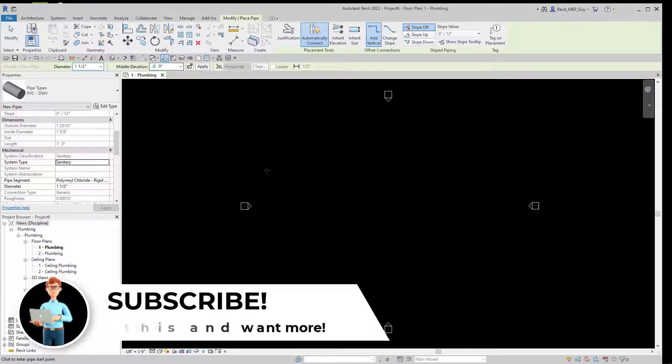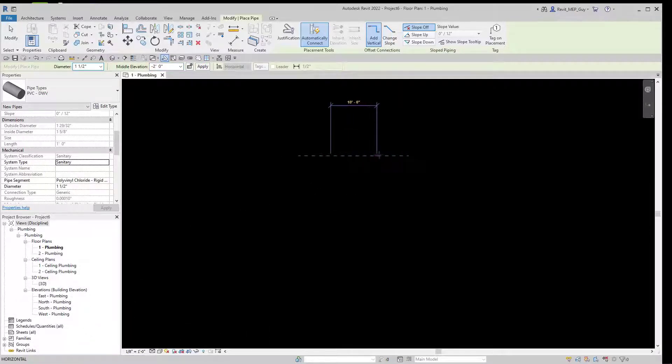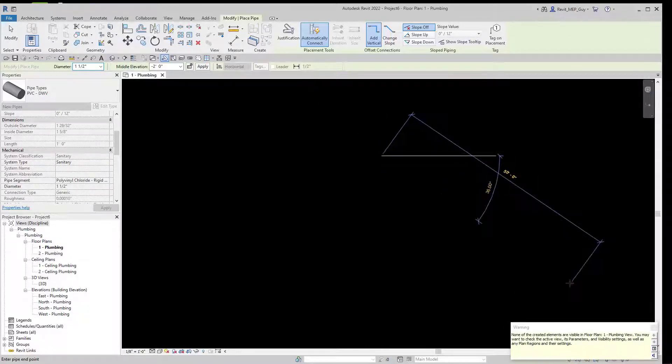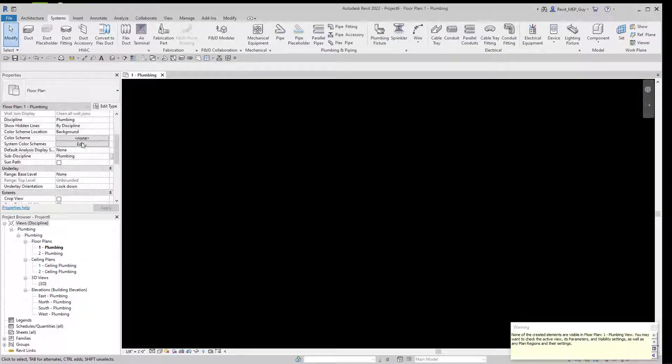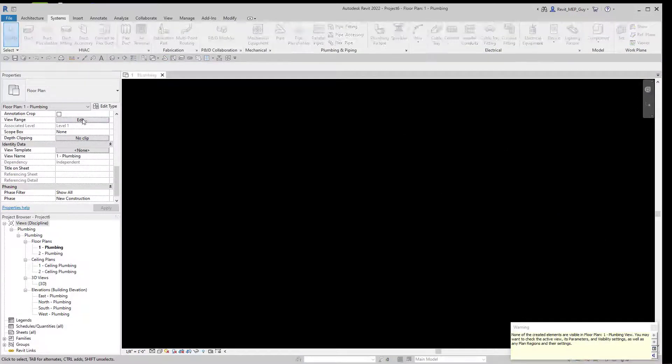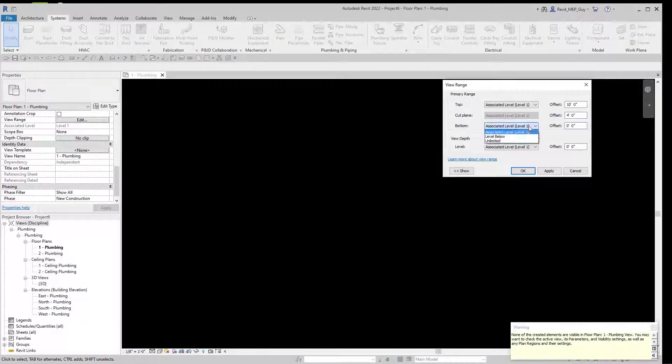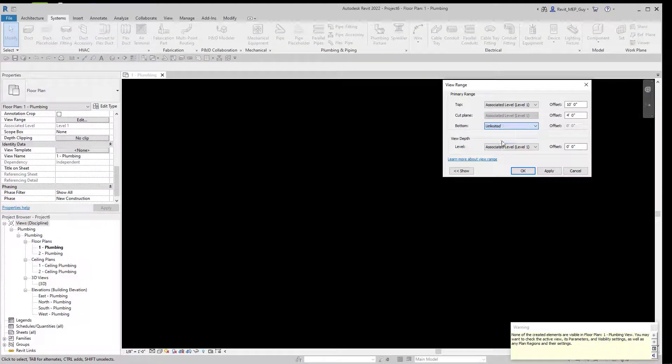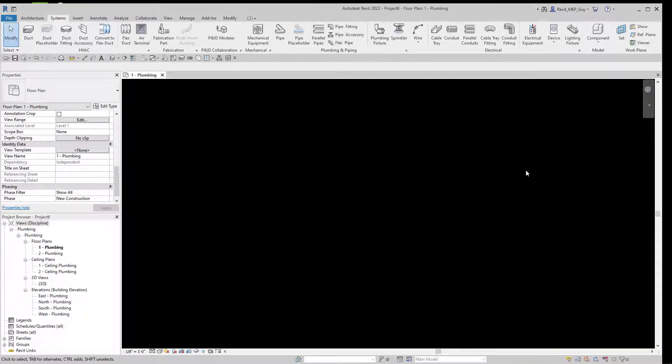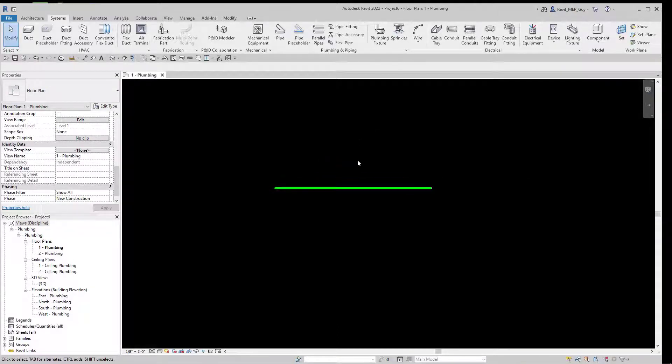To start drawing our pipe, let's draw it at negative two feet, since sanitary pipe is below the floor. Pick a point right here and we'll start drawing our pipe. We'll end it right here. As you can see, the visibility needs to be changed. Go to our view range, hit Edit, and make sure the bottom is set to unlimited and the view depth to unlimited. Hit OK, and now we can see everything below the floor.